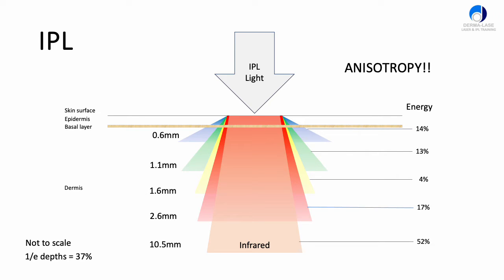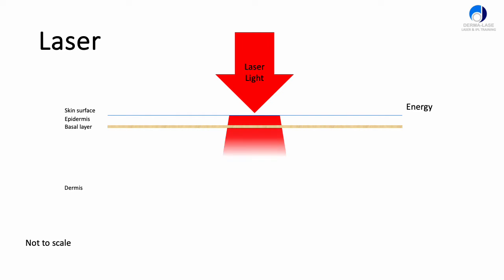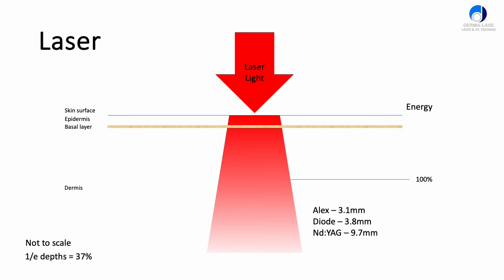How does that compare with laser energy? Laser light is just one wavelength — that's what lasers are good at, making single wavelengths, so all the energy is contained within that wavelength. The Alexandrite laser will penetrate to about 3.1 millimeters. Diode lasers at 808 or 810 nanometers penetrate down to about 3.8 millimeters. And the YAG at 1064 nanometers, similar to the 1200nm region with IPL, can go down to nearly 10 millimeters deep.